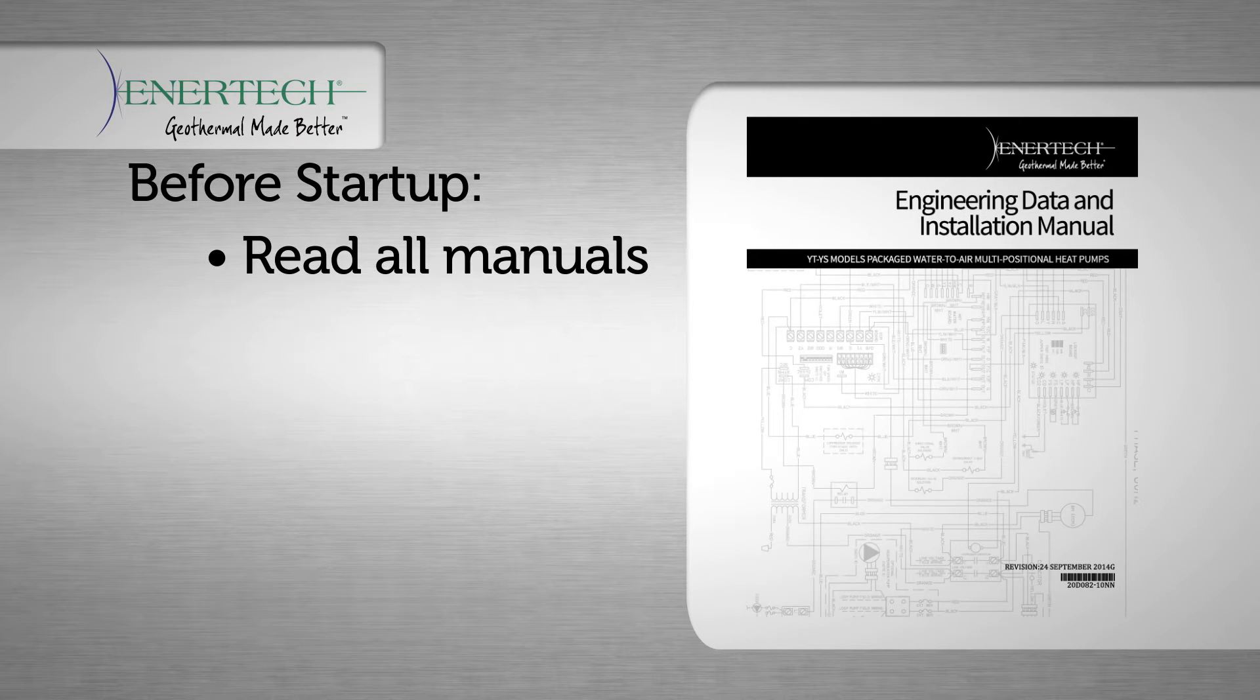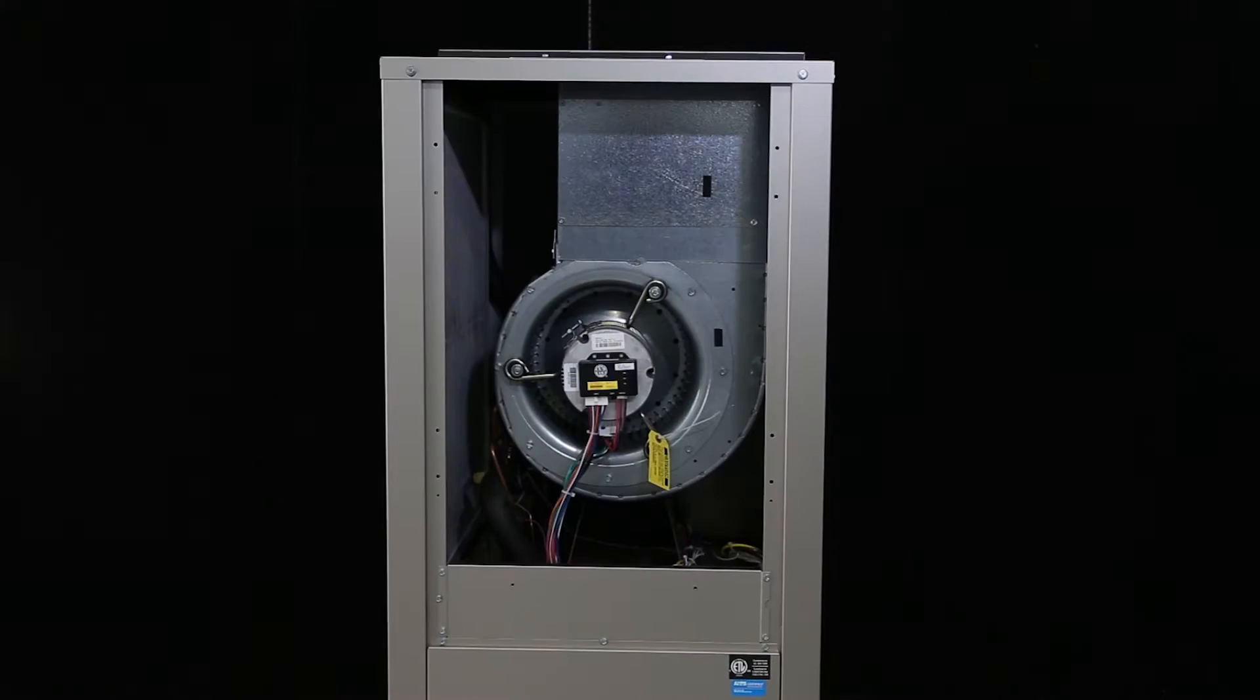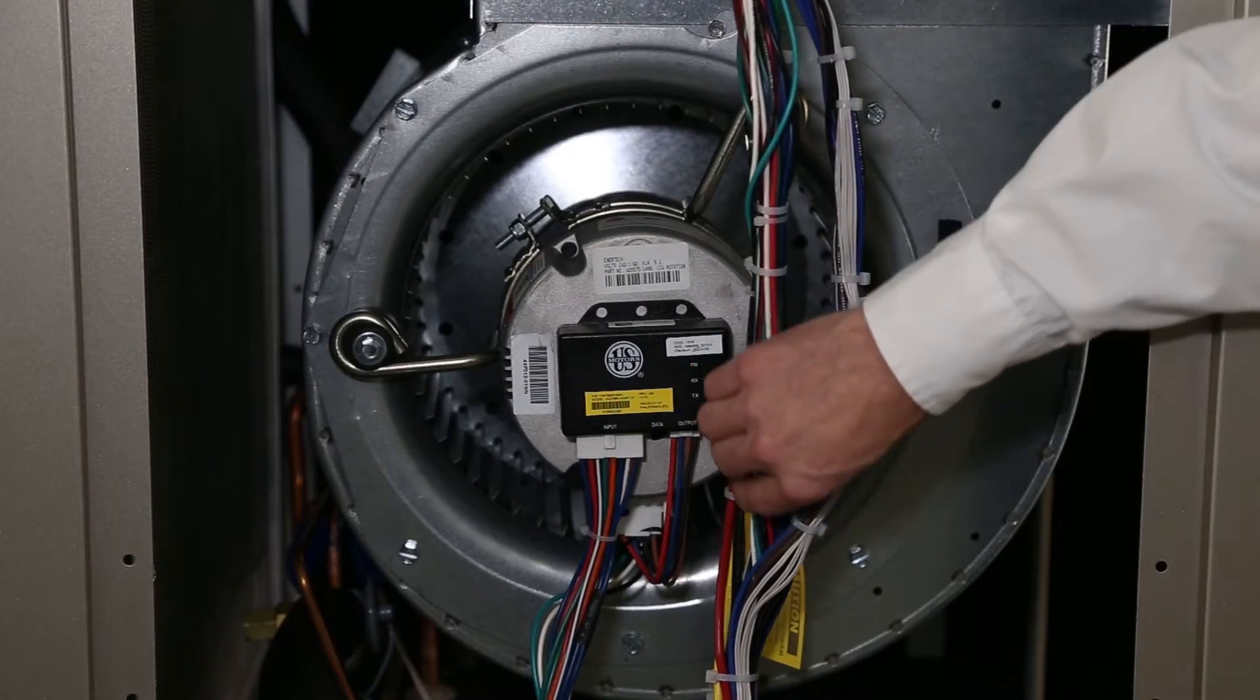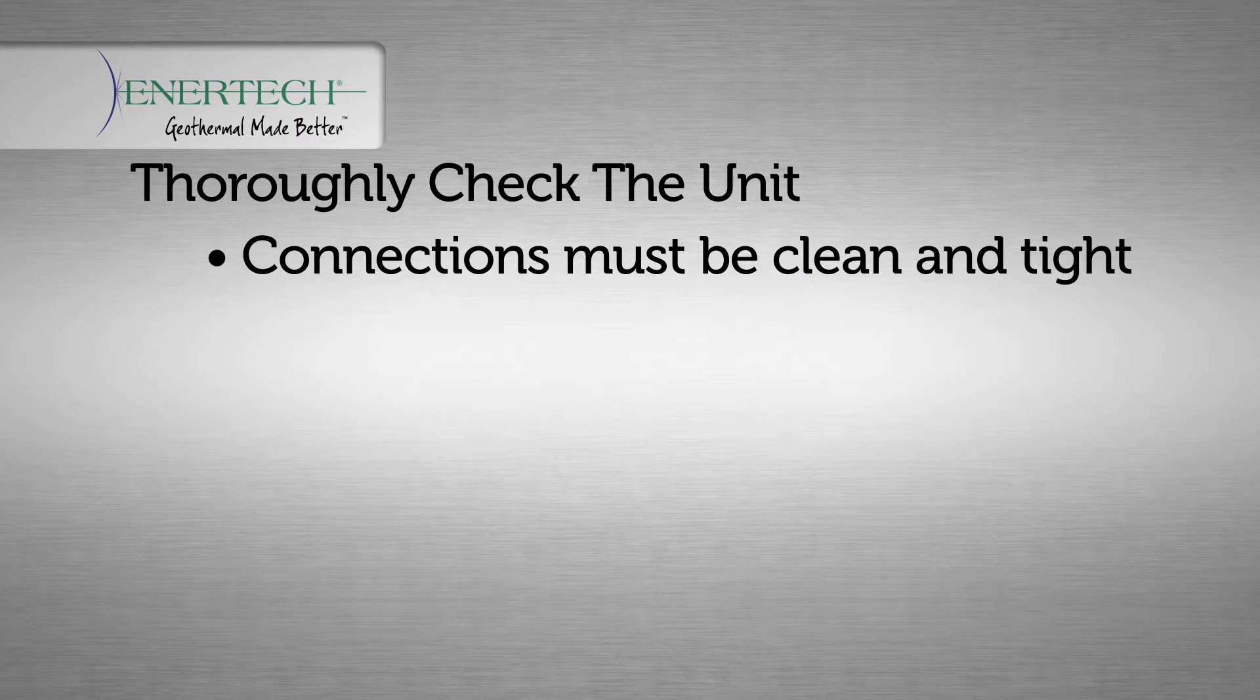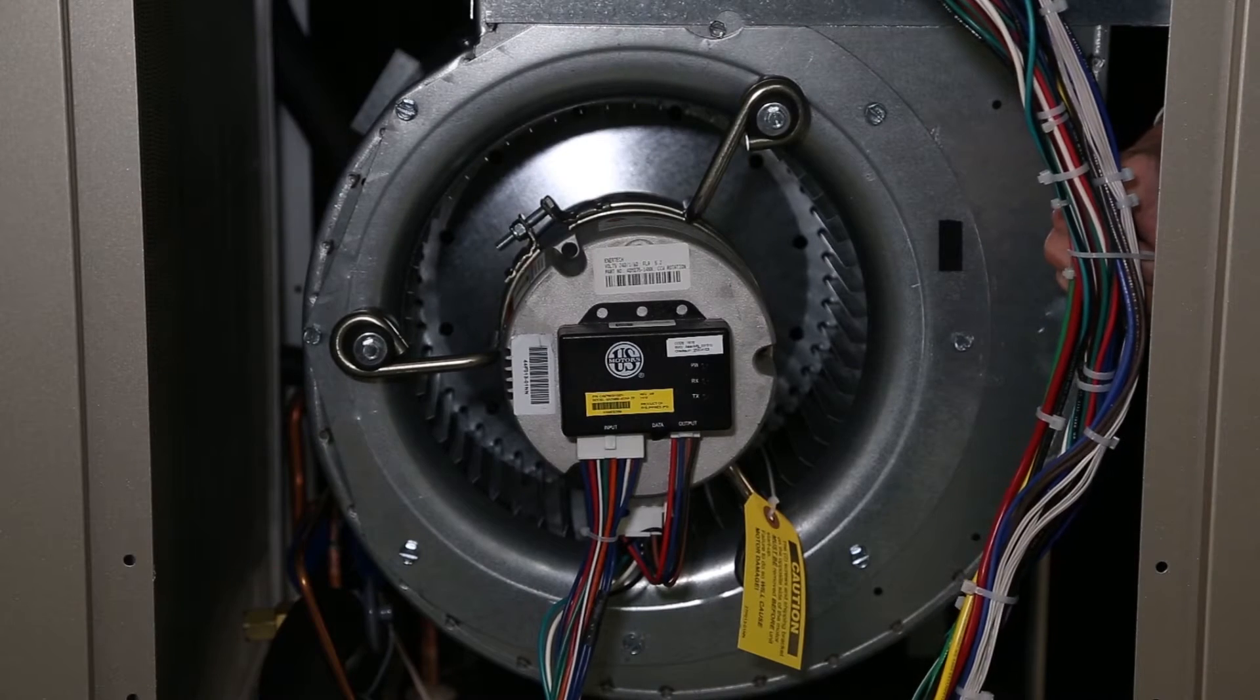Before unit startup, read all manuals and become familiar with the unit components and operation. Thoroughly check the unit before operating. Inspect all electrical connections and wires. Connections must be clean and tight at the terminals and wires should not touch any sharp edges or copper pipe.